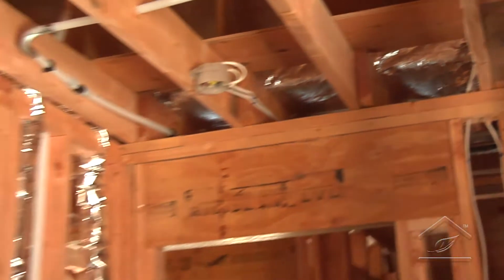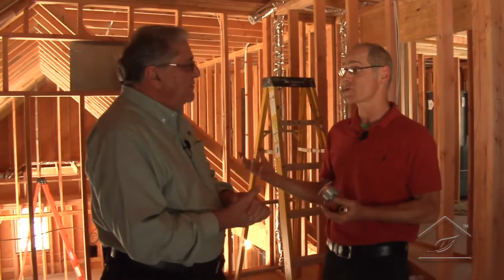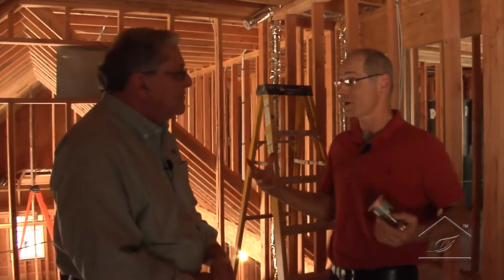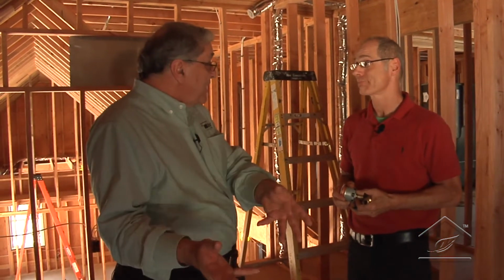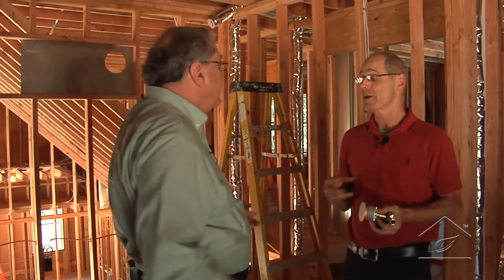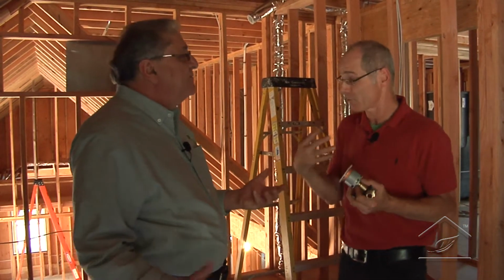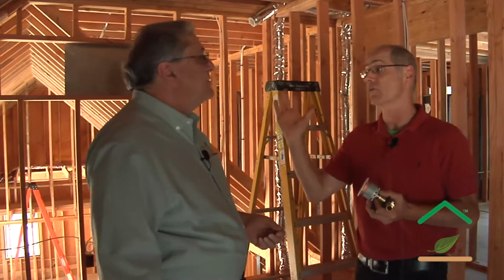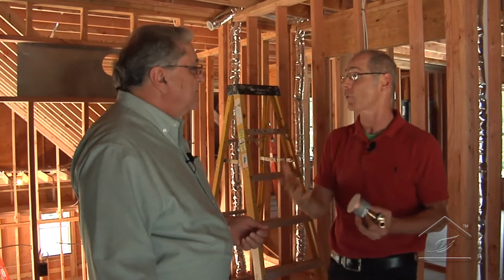Now Rich, we were just saying when we were upstairs, about the ventilation on demand. I have almost the same thought process here. I have a range hood that would be on top. I have a dryer. So I have to interlock or do something. When I turn this on and create a negative pressure, I have to make sure I compensate by something turning on to make up for that pressure being lost. So are you going to set up a control strategy so that when the unit is turned on downstairs, it'll activate the ventilation unit up in the attic? Well, right now the HRV is tied into those areas, and there's a boost that we can hit a button and it goes on high speed. That's okay, that'll evacuate things. But if I'm having a negative pressure situation, that's another thing we have to address. I'll have to look at that. Am I going to have a louver open somewhere to compensate for that negative pressure, because I've got a dryer with lint and high humidity? I want to get rid of that.